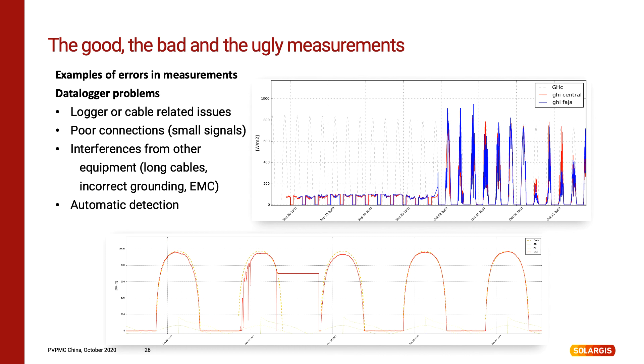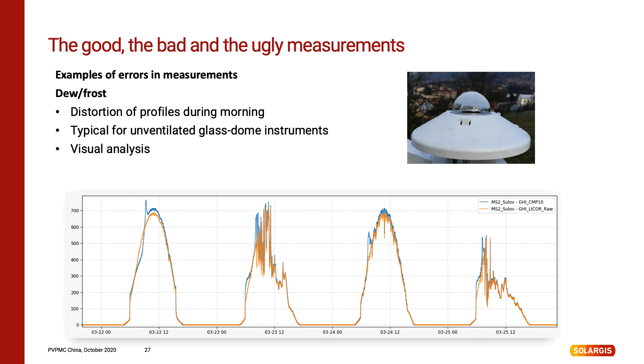DNI is calculated, and the consistency check is applicable only if you have separate measurements of all three components – global, diffuse and direct. Data logger problems are also possible to detect by both automatic and visual checks. Here we see several distorted days in the top picture and one distorted evening in the bottom picture. The source of these problems may be in the data logger itself. This can happen with wrong settings, overloaded inputs, bad cable connections or cable paths. If signal cables are tied together with power lines, high frequencies may induce into low-level signals and destroy the measurements. Dew or frost, as visible on the dome of this pyranometer, typically occurs during cold mornings where the glass dome is covered by small drops which distort measurements.